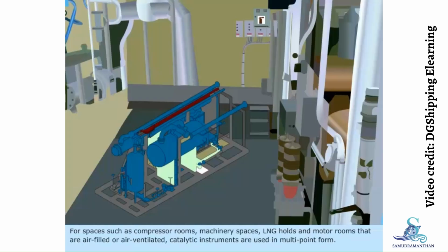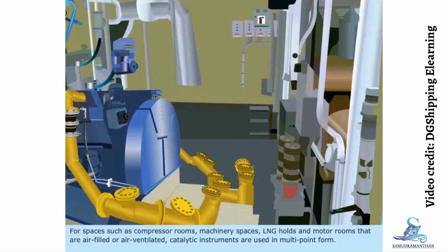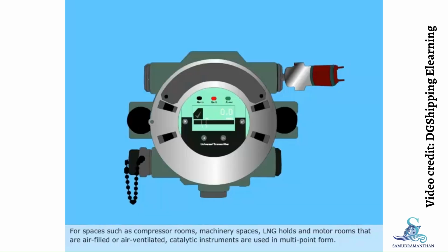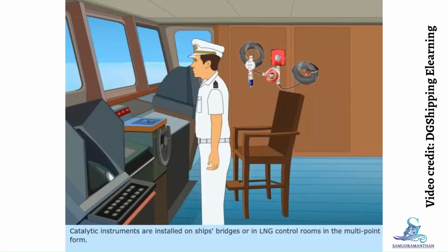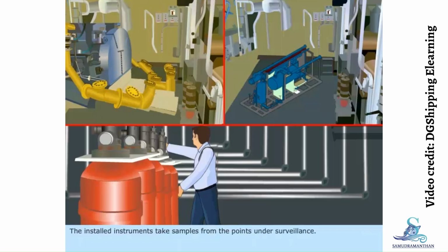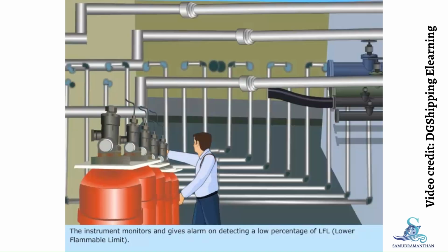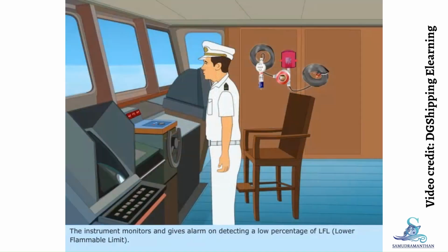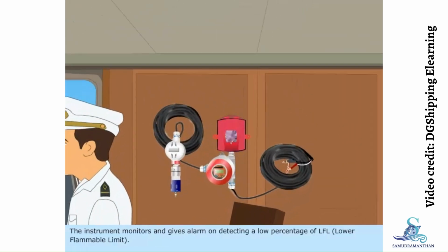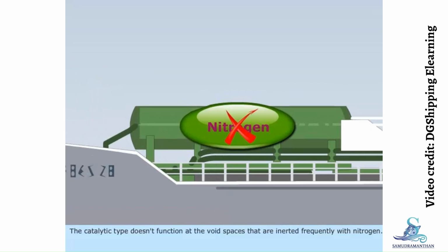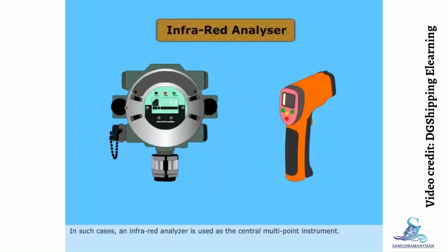For spaces such as compressor rooms, machinery spaces, LNG holds, and motor rooms that are air-filled or air-ventilated, catalytic instruments are used in multipoint form. Catalytic instruments are installed on ships' bridges or in LNG control rooms in the multipoint form. The installed instruments take samples from the points under surveillance. The instrument monitors and gives an alarm on detecting a low percentage of LFL, lower flammable limit. The catalytic type doesn't function at the void spaces that are inerted frequently with nitrogen. In such cases, an infrared analyzer is used as the central multipoint instrument.